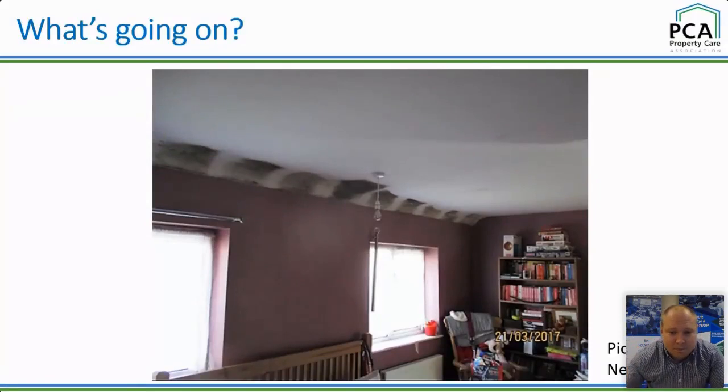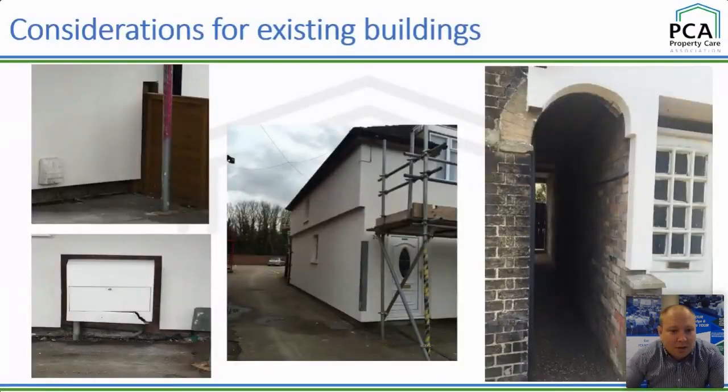And another slide just to illustrate this. So I'm hoping you're all sucking through your teeth right now. And I know many of you have probably seen a lot of these before. I know they were taken by Steve, and they show issues that are likely to result in differences in the cold bridges and elements of the building envelope that are going to result in condensation and mould growth problems.